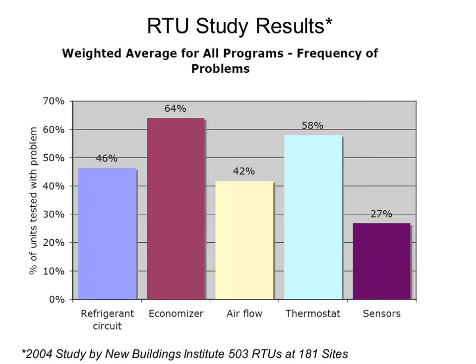And then, lucky for us, only half the time, 46% of the time, was the refrigeration charge wrong, and only 42% of the time was the airflow wrong. So those sound really good. And then the controls guys that put all the little sensors on the unit, they only did a bad job 27% of the time, right?